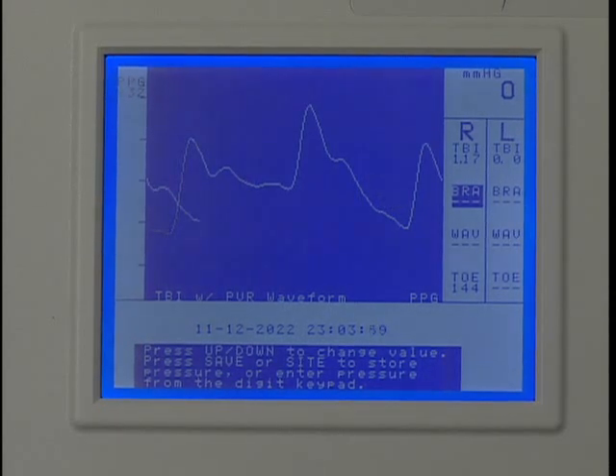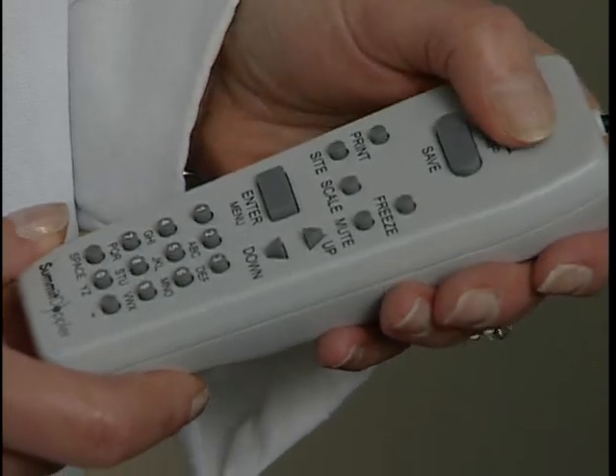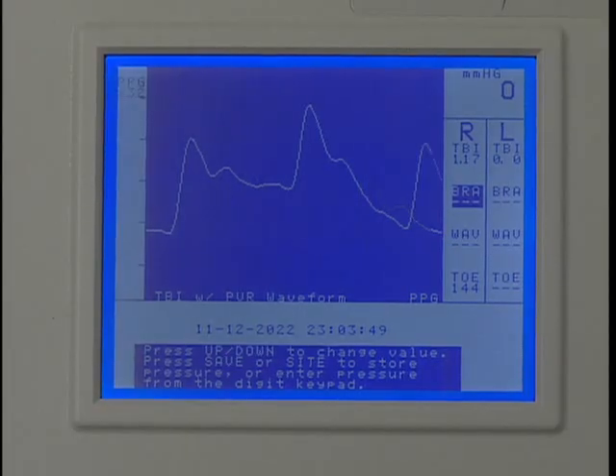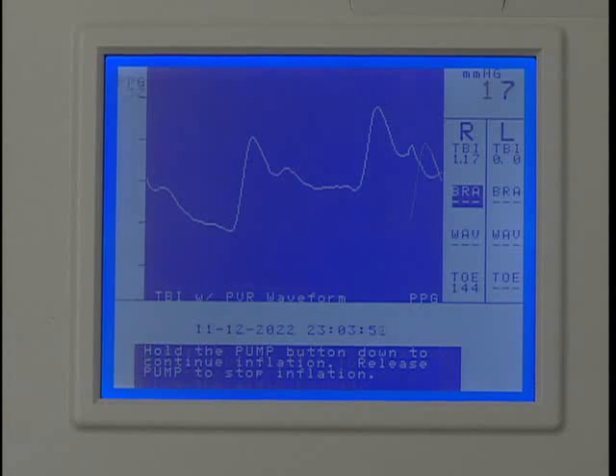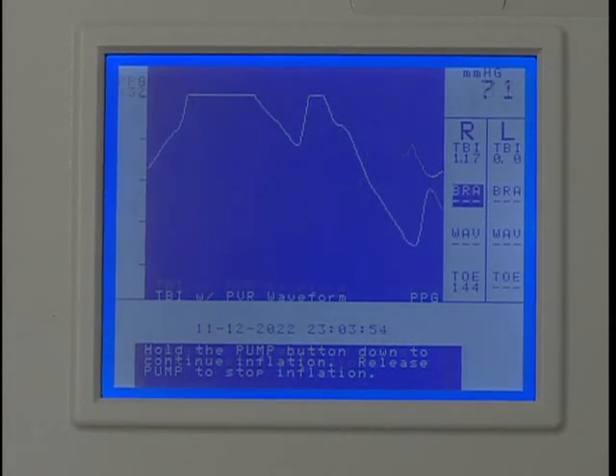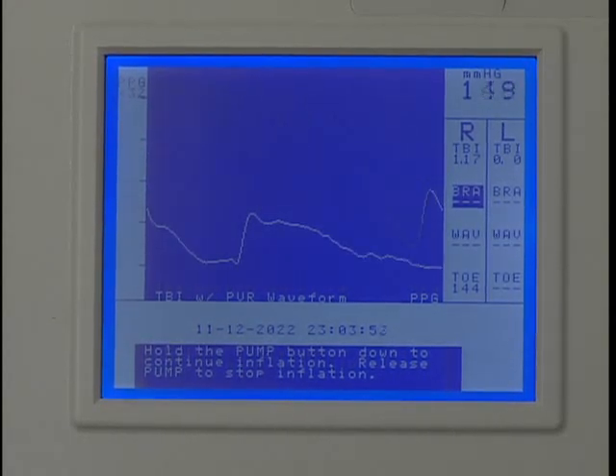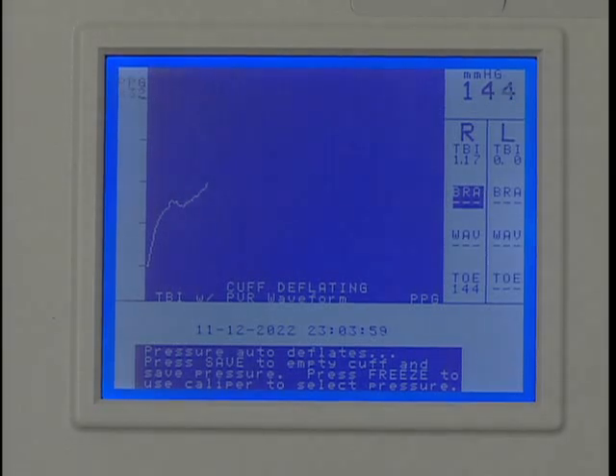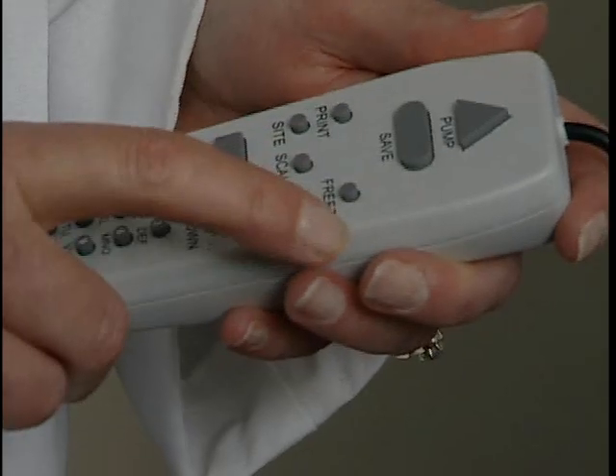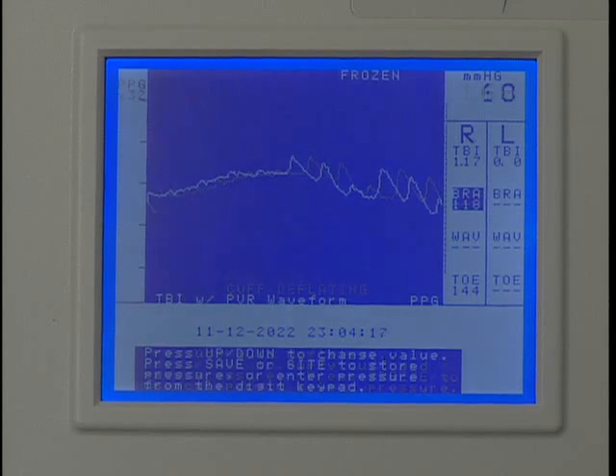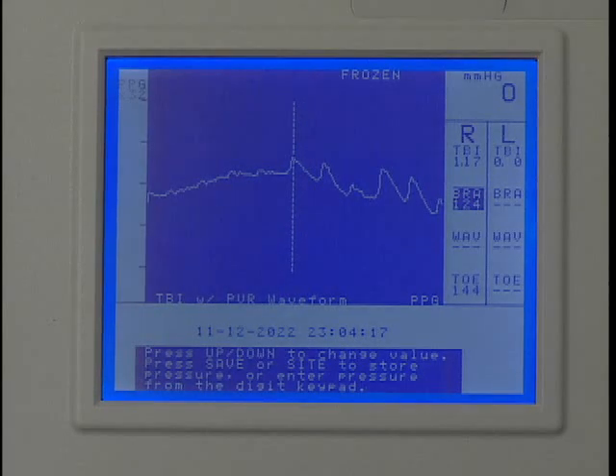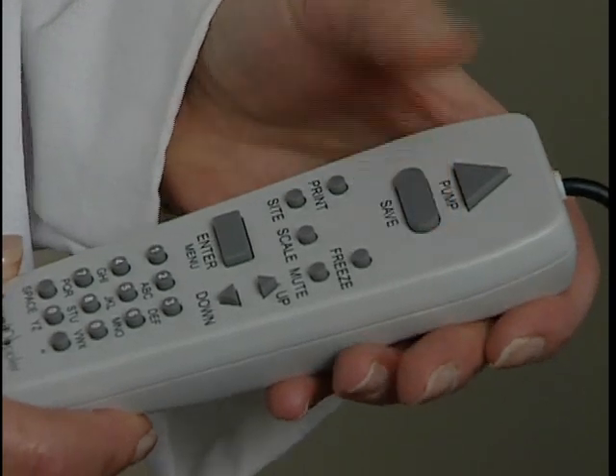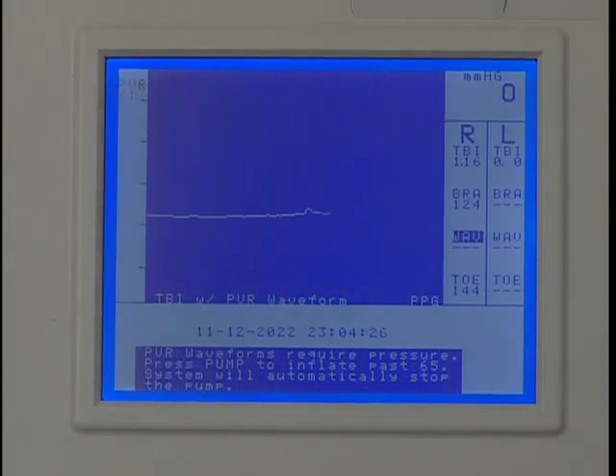Once a stable PPG waveform is obtained, press Pump to inflate the cuff. Continue to inflate to a pressure approximately 20 millimeters of mercury above the pressure where the PPG pulsations disappear. The cuff will begin to deflate automatically once the pump stops. Press Freeze after several pulses have reappeared. Press the up or down key to move the caliper tool to the beginning of the first upward slope at the start of the pulsation, as shown. This is the systolic pressure. Press Save to record it, and the marker will move to the next protocol location.